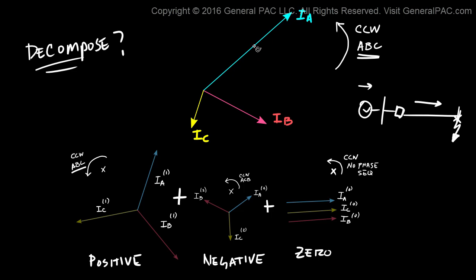Where the phase A current looked like that. Phase B current looked like that. And phase C current looked like that. Now can this relay in this breaker confidently declare that this right here is a line to ground fault. And more specifically it's an A phase line to ground fault.